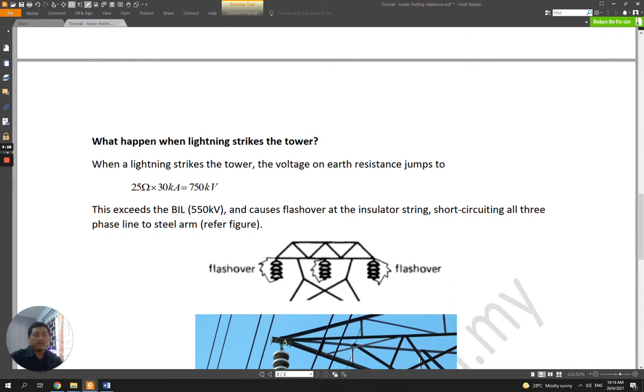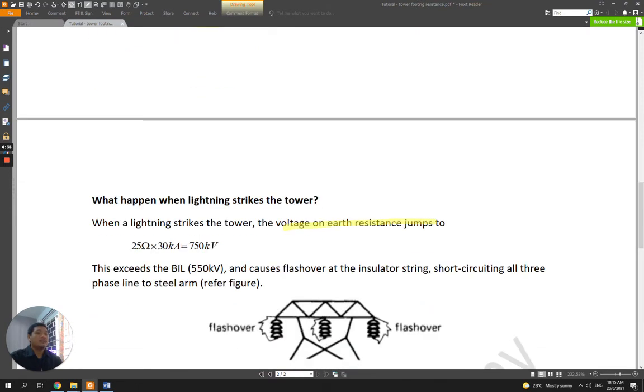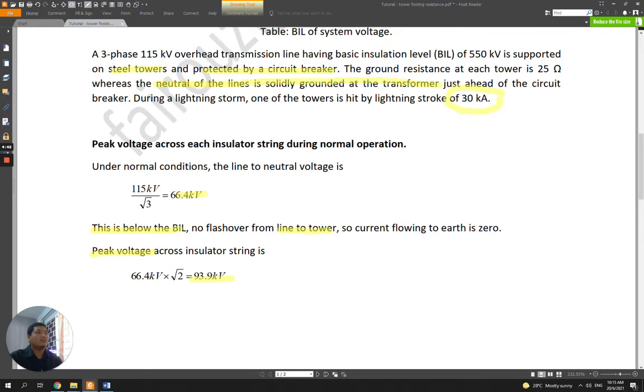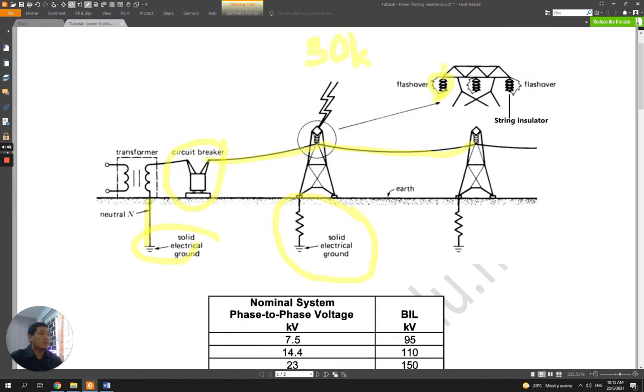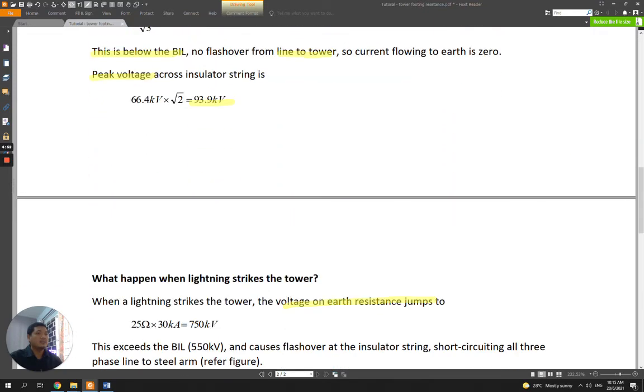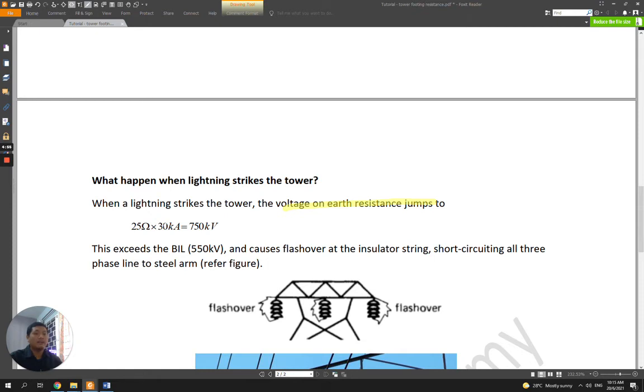So what happens when the lightning strikes the tower? When the lightning strikes the tower, the voltage on the earth resistance jumps to, you can calculate, simply V equals IR. So the voltage at the tower is 25 ohms times 30 kiloamp. The voltage at the tower is now 750 kilovolt. So this exceeds the BIL, which is 550 kV.